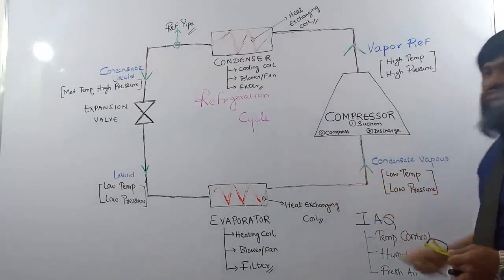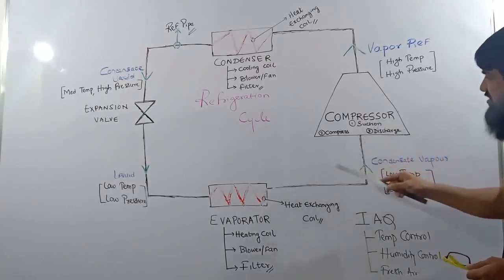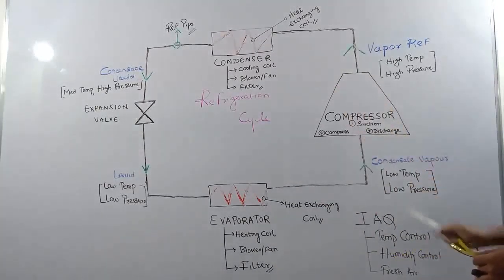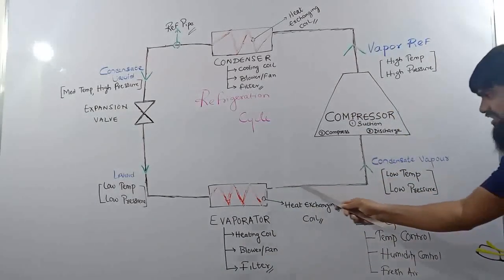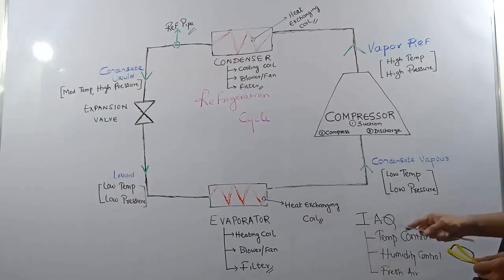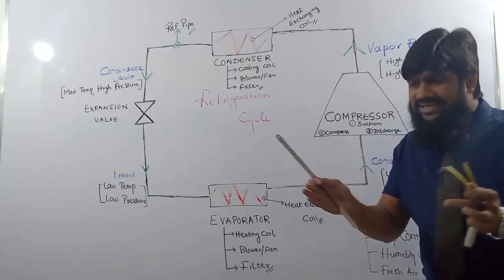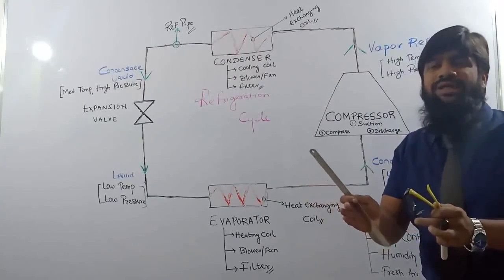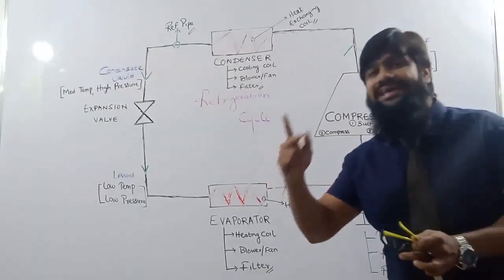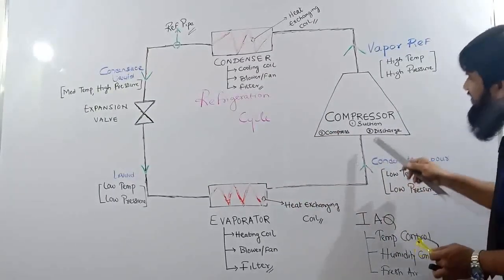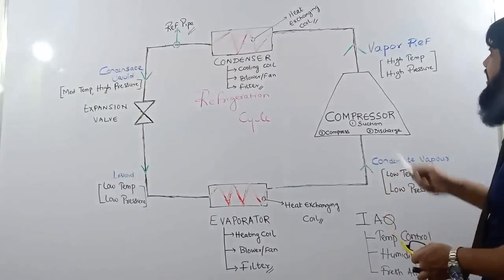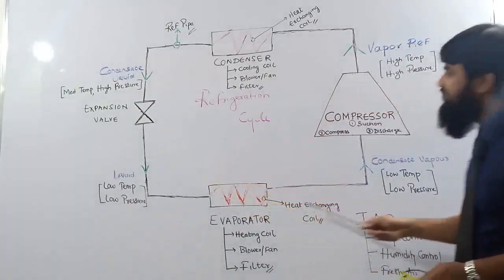The compressor does three things: suction, compression, and discharge of the refrigerant. The refrigerant is a fluid with which we can carry out heat exchange and maintain the required temperature of a room. While sucking the refrigerant coming from the evaporator, the compressor receives it at low temperature and low pressure. As we know, whenever you compress a gas, not just pressure but temperature also increases.